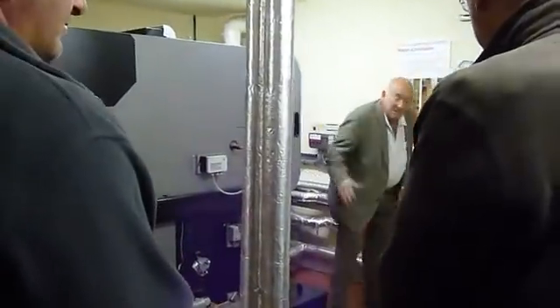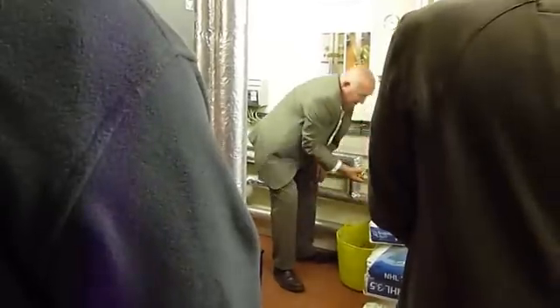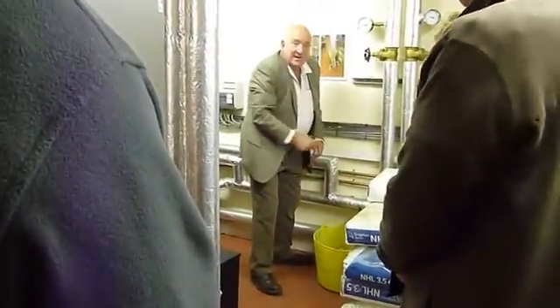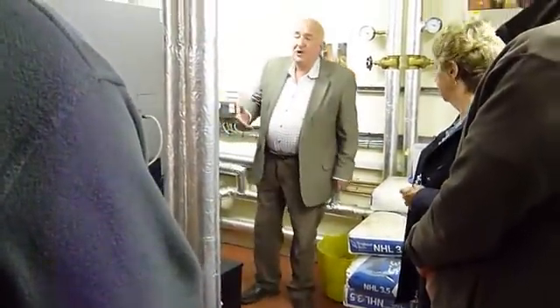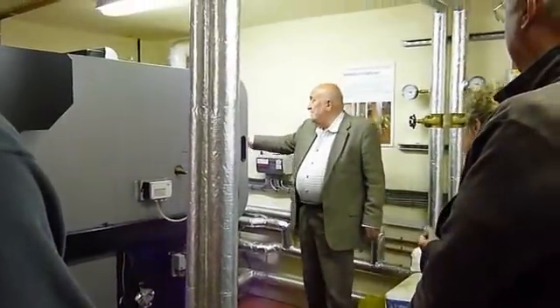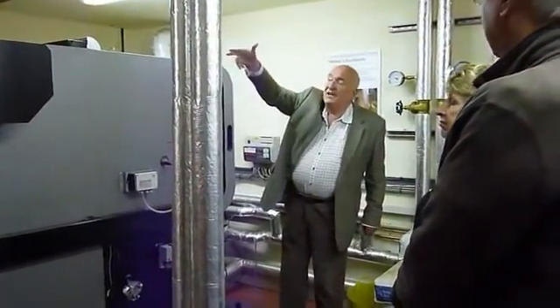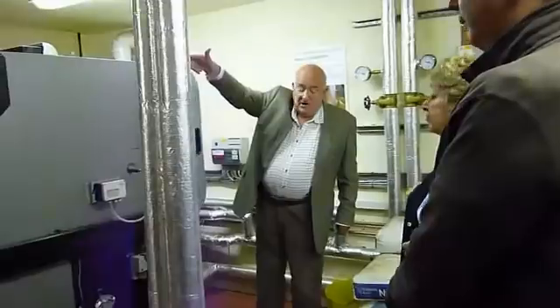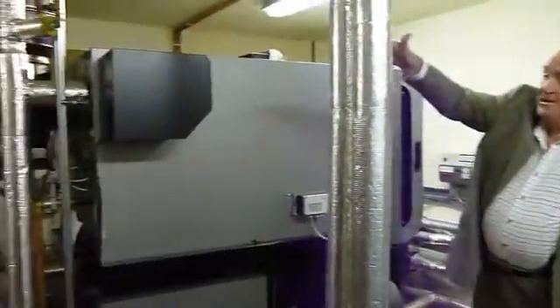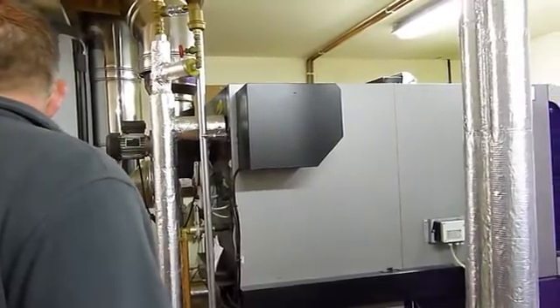There isn't a British manufacturer that produces anything as good as this. That's the chip, just ordinary softwood chip from any combination of trees. It's dried, it mustn't be more than 30% moisture, and it's fed in by an auger from the tank at the back. When the sensors detect a drop in temperature from the two holding energy cylinders, that's the energy bank there, those two 1500 litre cylinders, it fires up the boiler and generates energy.